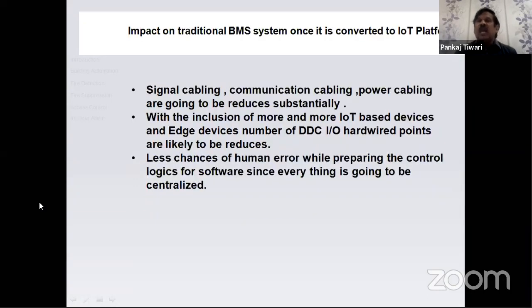When you talk about the IoT-based platform for the BMS, definitely a lot of signal cabling, communication cable, and power cable - we run kilometers of cables in a hospital for signal, communication, and power. Hopefully most, not all, but most of them are going to go away. With the inclusion of more IoT-based devices and machines, the number of direct digital controllers and the IO input-output hardware points are likely to be reduced drastically.